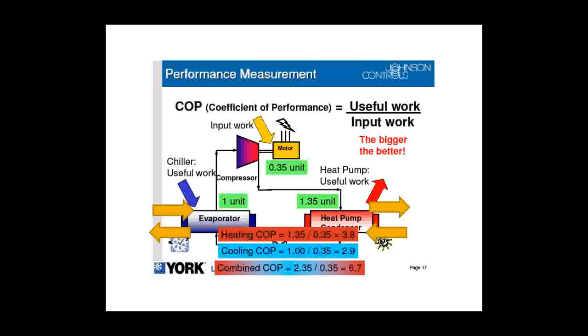This is basically a cross-section of, or a working diagram of, those heat pump chillers. We're producing hot water on the condenser side, chilled water on the evaporator side, and what's remarkable about the project is developing a coefficient of performance nearly 7. So one input of energy gets 7 out. When you combine the operation together, this is a diagram of how it all connects.